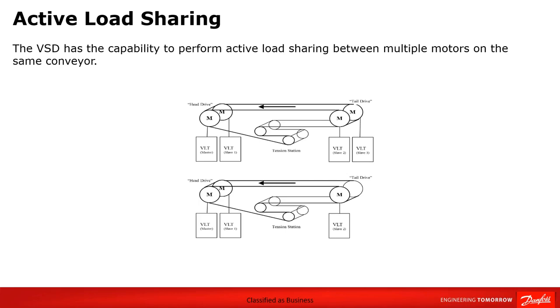So what does that mean? Well, it allows the follower to contribute more torque to the load. And then the same in reverse: as the master's torque decreases, the follower's torque limit also decreases, so it contributes less torque to the load. In this way, an even load sharing is maintained between multiple parallel VFDs, the variable speed drives, on the same load. And this sharing can be fine-tuned through what we call PID loops to obtain an accurate sharing of torque within a small bandwidth.